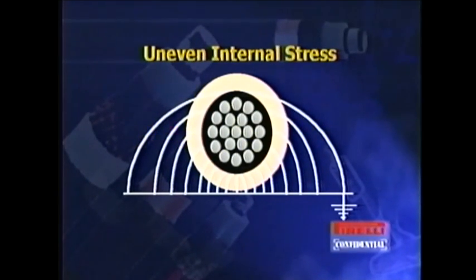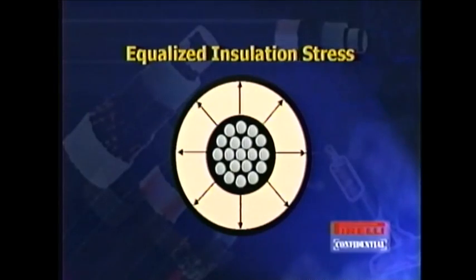This will cause the voltage stress within the cable to be asymmetrical or unevenly distributed, meaning that one part of the cable will be subjected to a much higher voltage stress than another. If this were the case, you may as well buy egg-shaped cable, and hopefully we don't create any of that. So what we do to prevent this from happening is extrude a semiconducting material around the circumference of the cable. This is called an insulation shield, and it's a semiconducting material. By doing this, we have a conductive material around the circumference, and we have an equalized insulation stress within the dielectric.